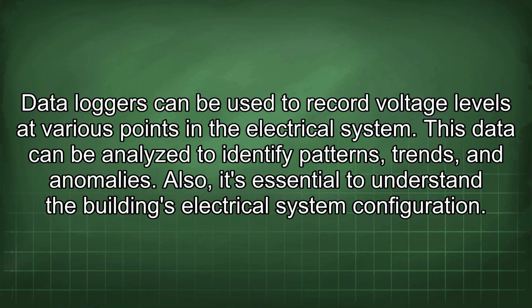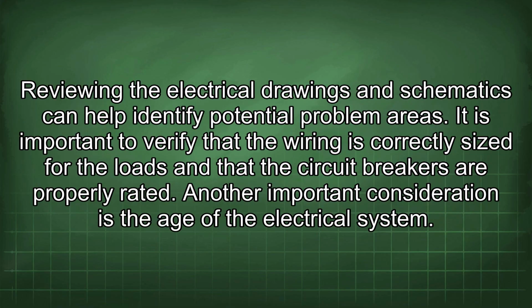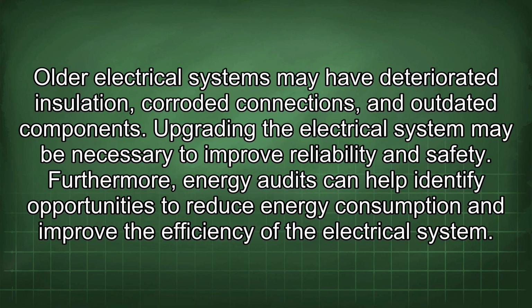Also, it's essential to understand the building's electrical system configuration. Reviewing the electrical drawings and schematics can help identify potential problem areas. It is important to verify that the wiring is correctly sized for the loads and that the circuit breakers are properly rated. Another important consideration is the age of the electrical system. Older electrical systems may have deteriorated insulation, corroded connections, and outdated components. Upgrading the electrical system may be necessary to improve reliability and safety.